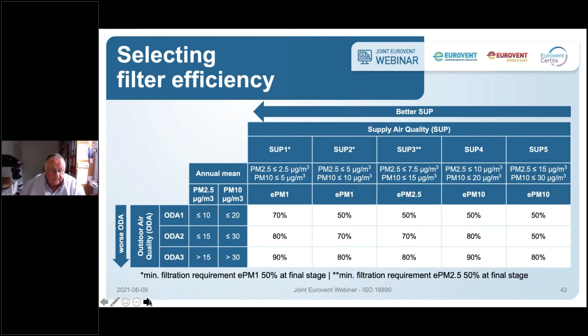That's quite easy. But what I can also do, in case of a multi-stage filtration, I can have an EPM1 60% filter, and in front of that an EPM1 50% filter, because when these filters are in a row, the final filtration is on an EPM1 80% level.